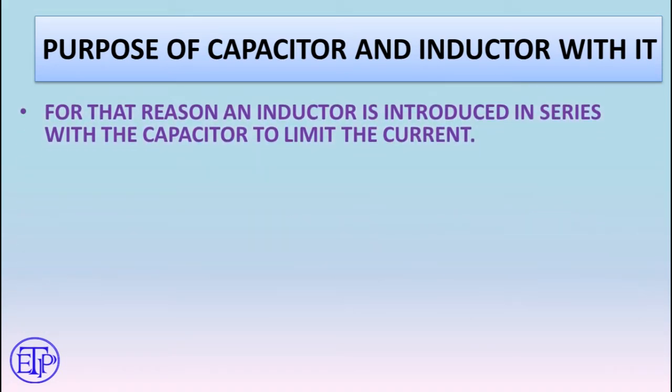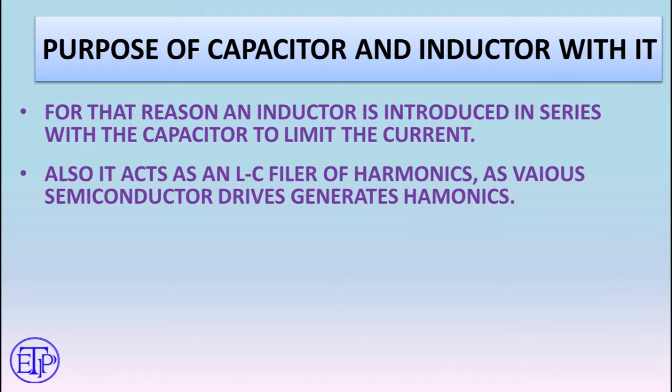For that reason, an inductor is introduced in series with the capacitor to limit the current, because we know that an inductor opposes sudden change of current. Another interesting thing is that this kind of arrangement — a capacitor in series with a reactor — acts as an LC filter for harmonics.